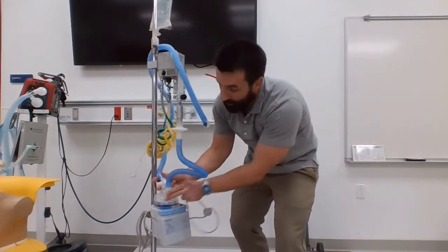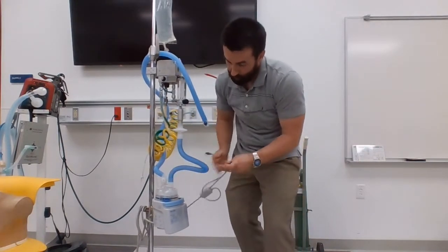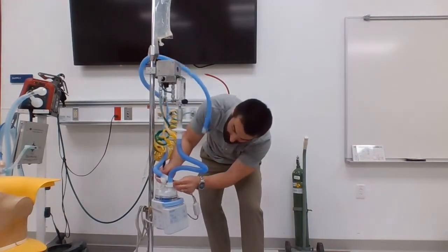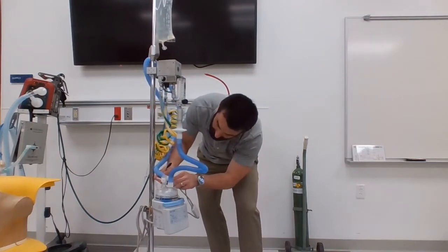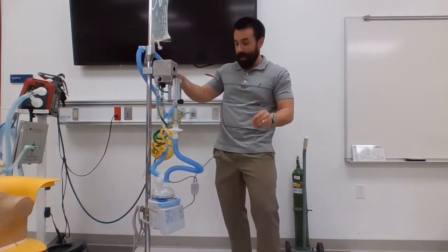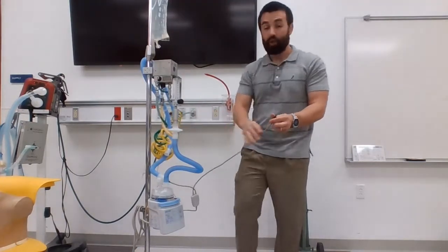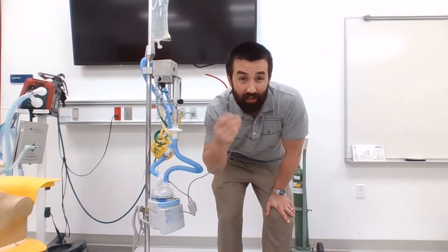That is going to hook up to this. The short one is going to hook up right into the back side of that inspiratory line, or that gas line going to the patient, and that's going to charge it. We can leave this one hanging on the Optiflow. This long two-pronged one is for the expiratory side, for when we get into heated wire ventilator circuits where we have an inspiratory and expiratory.